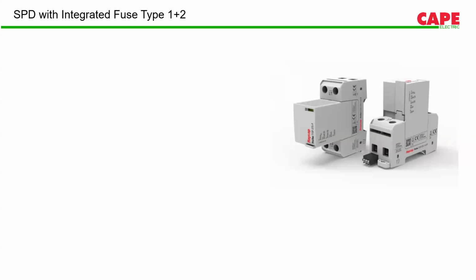What we can do is use SPDs which have an integrated fuse. So these can be type 1 and type 2 SPDs. Again, these SPDs are also tested with the standard IEC 61643 part 11 2011. One more thing I would like to add here is that the same IEC 61643 part 11 2011 has been adopted by the Indian standard IS also, as IS 16463 part 11 2016.